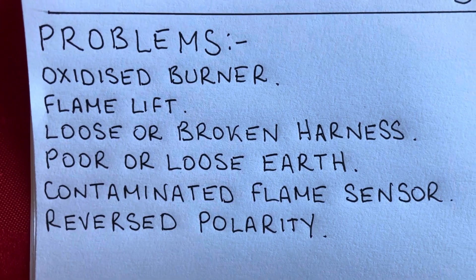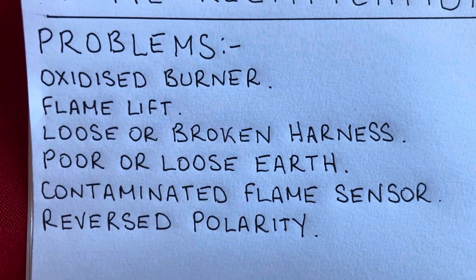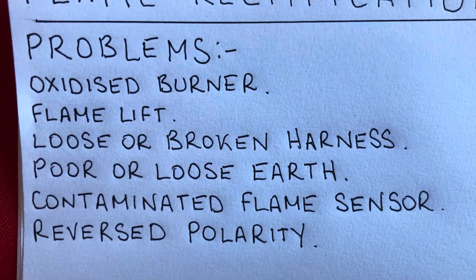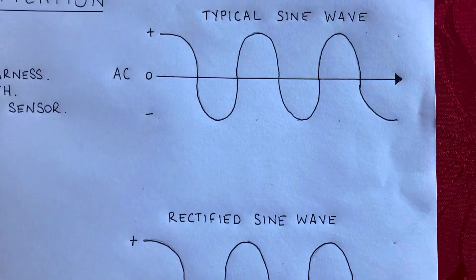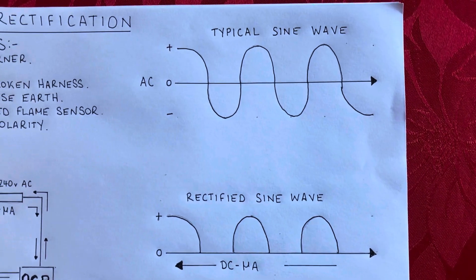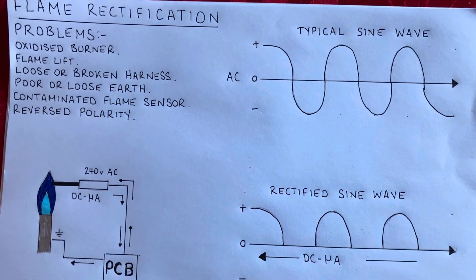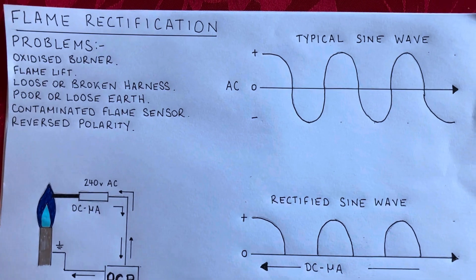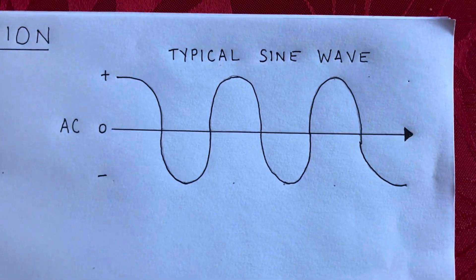The last main cause is reverse polarity — that's when your live and neutral are crossed. It's a bit like crossing the flow and return pipes on a central heating system: the water still flows, just the opposite way around. With reverse polarity your 240 volts is coming in on the neutral and going back on the live instead of the other way around.